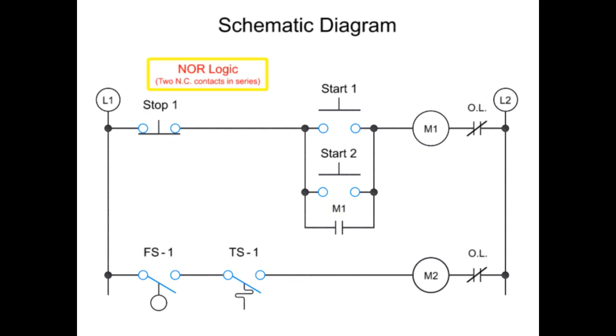NOR logic, an extension of NOT logic, operates by the inclusion of a second, normally closed push button in series. In this arrangement, pushing stop button 1 or stop button 2, the M1 coil is shut off, and the M1 holding contact is deactivated.